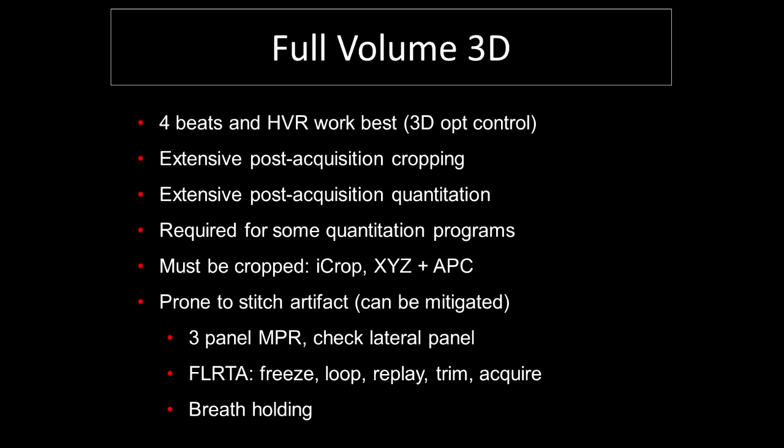Full volume 3D is large volume imaging — you can include all or mostly all of the heart. However, it requires cropping and provides capabilities for extensive post-acquisition quantitation, especially RV and LV volume. For a number of quantitative programs, you must do a full volume 3D — it will not work with Live or Zoom. The problem with full volume 3D is that it's prone to stitch artifact, so you have to use the three-panel MPR display and check the lateral panel.